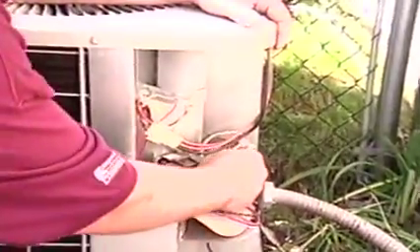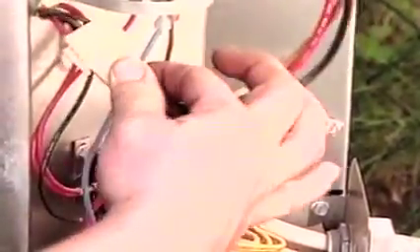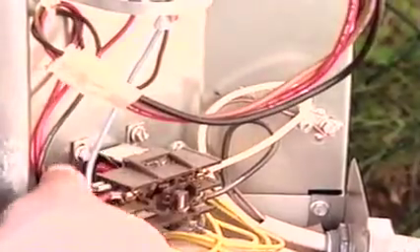Because the circuit breaker tripped immediately after being reset, it's logical to suspect that there is a short somewhere in the unit. Next, look for obvious signs that could create a direct short, such as loose, burnt, or broken wires that could be touching the case of the unit, or burnt controls which could have shorted. In this case, everything looks okay.